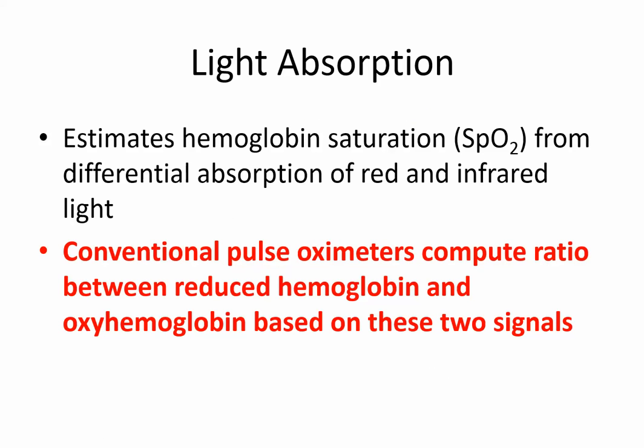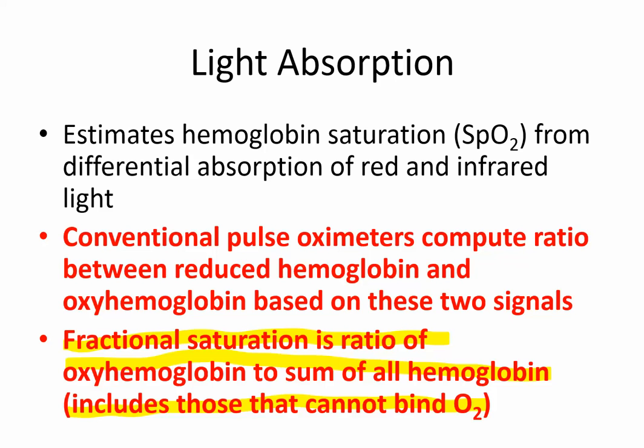Conventional pulse oximeters compute the ratio between reduced hemoglobin and oxyhemoglobin based on these two signals. The fractional saturation is the ratio of oxyhemoglobin to the sum of all hemoglobin, and that includes those which cannot bind oxygen.